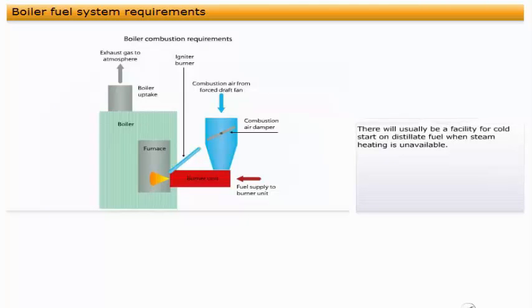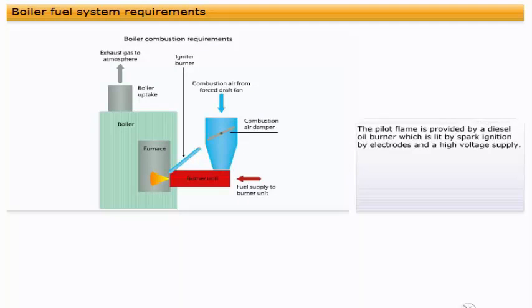There will usually be a facility for cold start on distillate fuel when steam heating is unavailable. A pilot flame is used to ignite the main burner. The pilot flame is provided by a diesel oil burner, which is lit by spark ignition by electrodes and a high voltage supply.